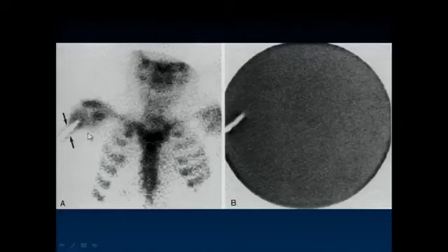Here's a patient with a cross right on their necklace, right, that metal attenuating there. Here's a nice cracked collimator. You see it as an artifact. You might think the patient has a metallic rod in their femur or something, but you notice when you do the flood there, it still exists, so a cracked collimator.